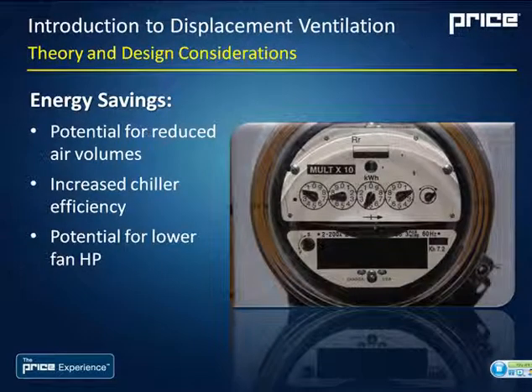Other energy savings that are available with the displacement system are that there is a potential for reduced air volumes, and this is mainly in spaces where you would see high ceilings. Because displacement conditions the occupied zone only, which is that lower 6 feet of the room, if you're looking at a room like a school gym or an auditorium, theater, something like that with a very high ceiling, you're actually only conditioning, or concerned about conditioning, the lower 6 to 7 feet of the room.